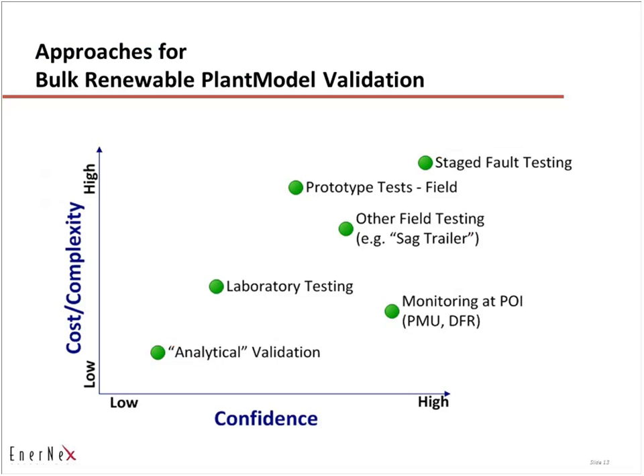When we talk about renewable plant model validation for significant grid disturbances — large-signal events where voltage might change by 25, 30, or 40 percent rather than a few percent — you get deeply into the control operation of the plant and potentially other equipment like static VAR compensators. In terms of validating the entire plant from the outside, there are some ways to approach it.